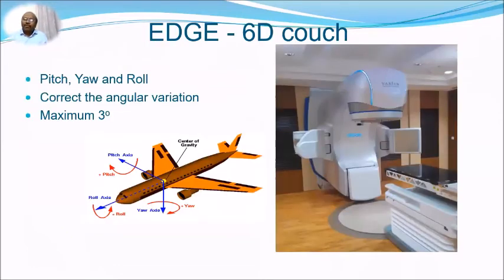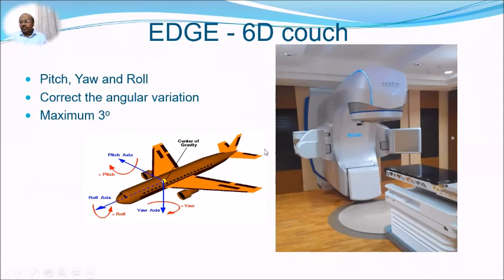A 6D couch is not an absolute necessity for SBRT but is useful if available. It can correct for translational and rotational errors — pitch, yaw, and roll — with a maximum correction of approximately three degrees.